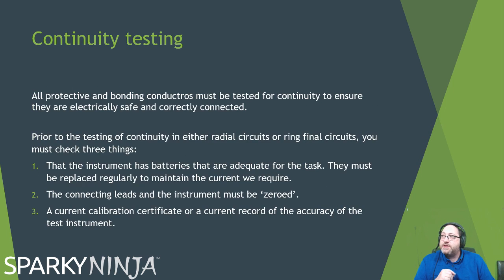Alright, so with continuity testing, start at the basic tests here. All protective and bonding conductors, or conductors, must be tested for continuity to ensure they are electrically safe and correctly connected.